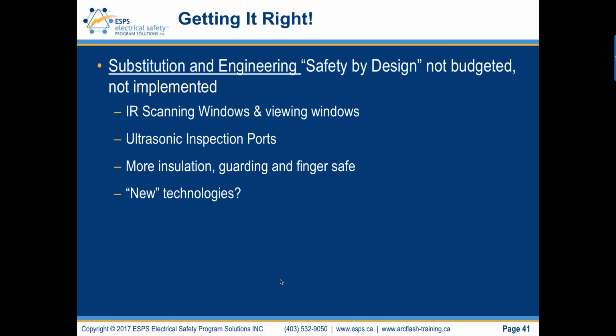IR scanning windows and viewing windows, they're being installed en masse. Awesome, right? So we don't have to, you know, remove bolt-on covers to do a scan. Ultrasonic inspection ports. If you're not using ultrasonic, you should consider it. Not only can we look for hot spots, but we can try and hear, right, with ultrasonic technology, that arcing faults are occurring before they become a full-blown arc flash. So I encourage you, if you haven't looked at ultrasonic testing, that you do review that, but you can get ports for that too. More insulation, guarding and finger safe in newer equipment than in the past for shock, you know, and reducing shock risk.